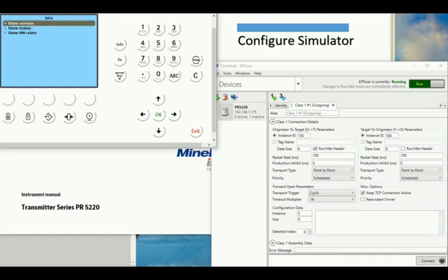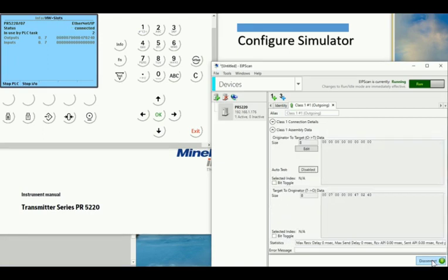So there's a screen that we can monitor by looking inside the info button, and then we navigate down to hardware slots and we take a look at our Ethernet IP card. In there you can see the status says waiting for a connection. Next thing we're going to do is press connect, and now you can see that the status has changed to connected. Okay, if you look at the weight, we're not really getting the weight yet because we haven't asked for it.